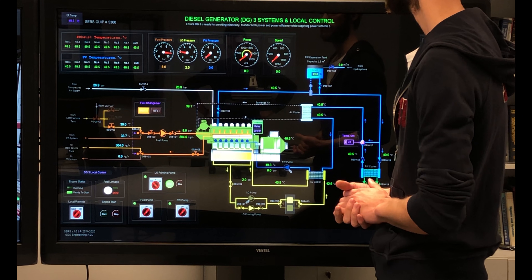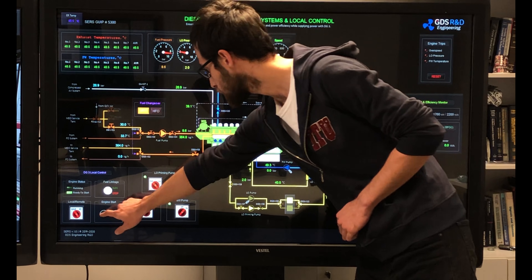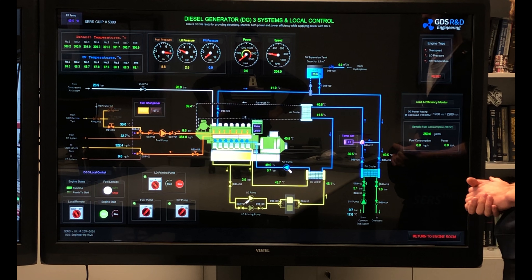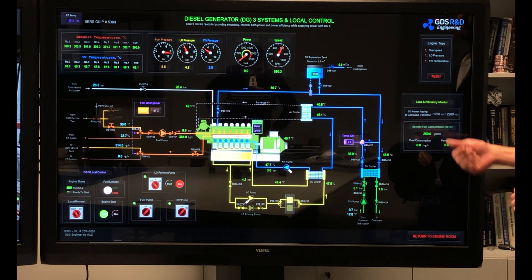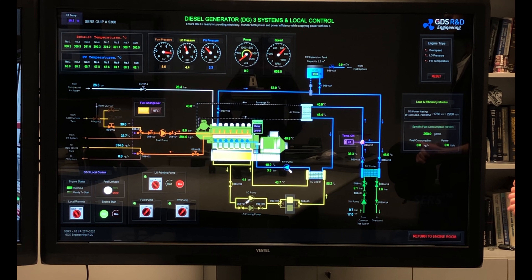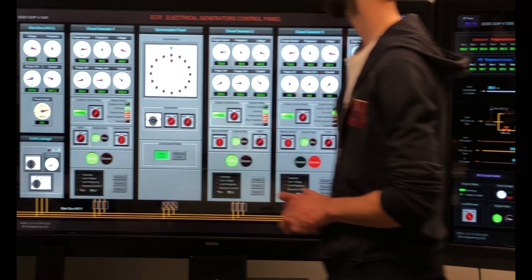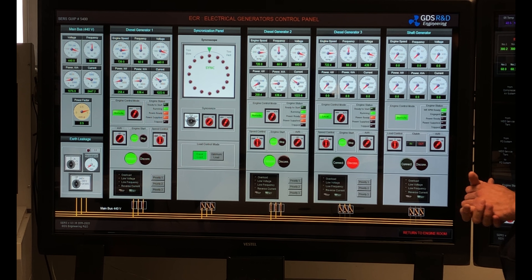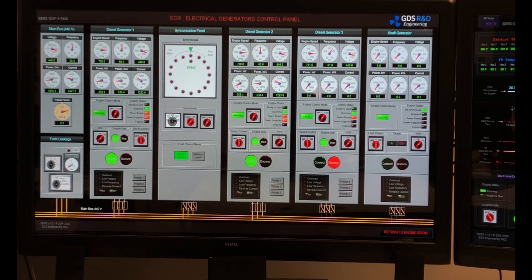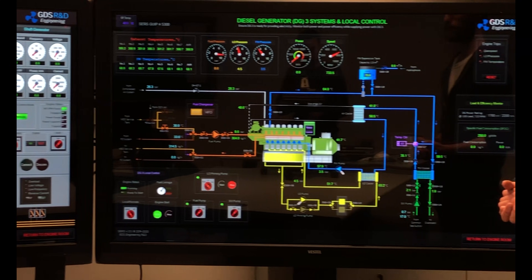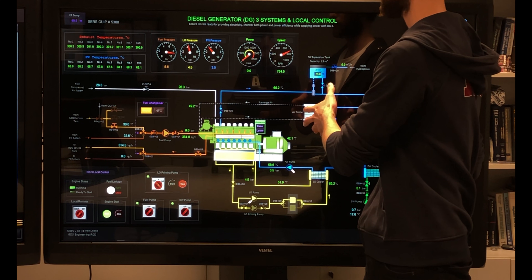The fuel linkage is in run position and I see the ready-to-start light. I will start this diesel generator in local mode and switch the control mode to local. Everything looks good and I will start the engine. The engine speed is rising and it is supposed to be around 720 RPM. I will set up my power generator system to synchronize the third diesel generator and feed the bus bar with it. All parameters of diesel generator 3 look good and I will switch the control mode to remote so I can synchronize diesel generator 3 from the engine control room.